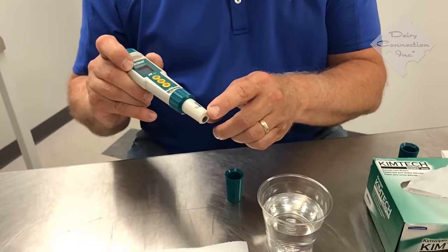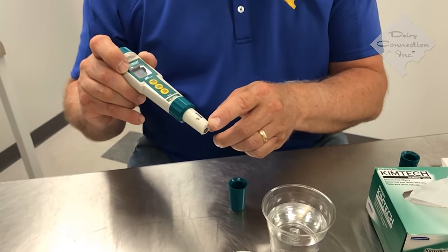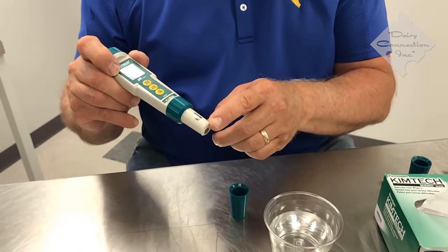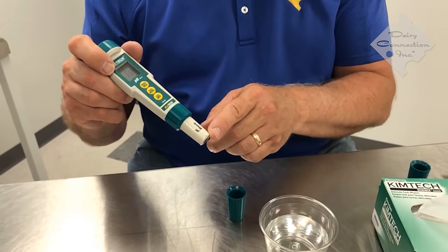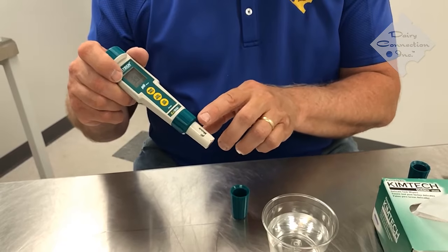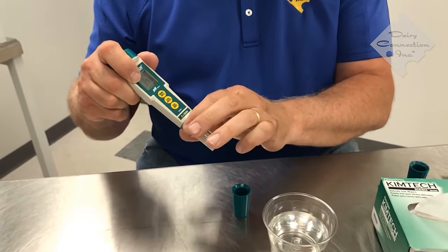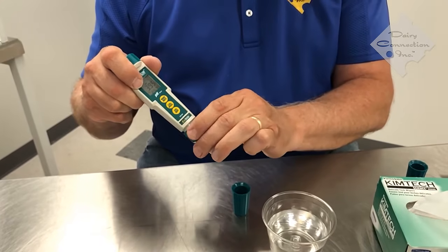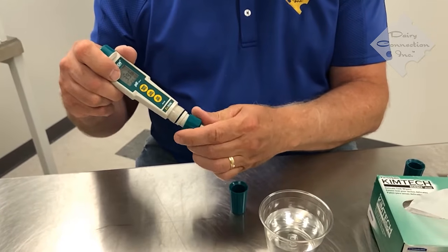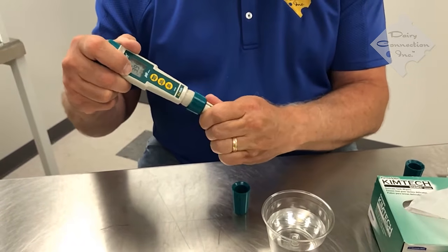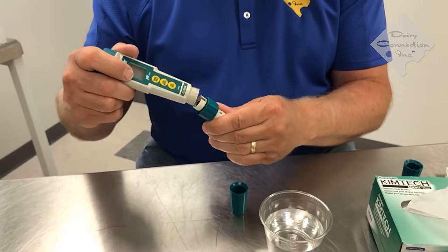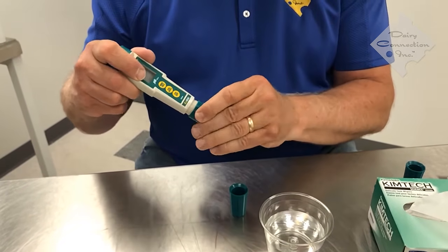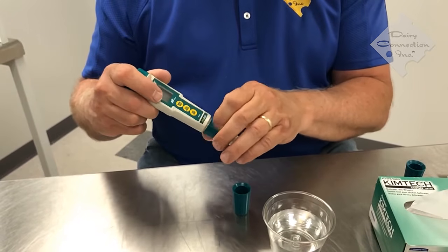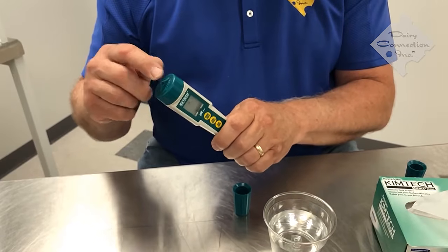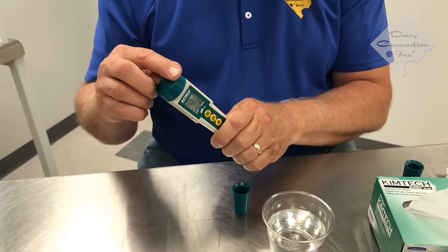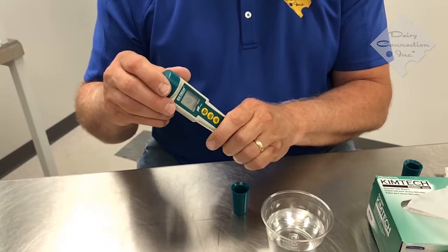And this is the critical point of maintenance of your pH electrode, of keeping it clear of calcium and protein and fat that are inherent with dairy products. If you're going to have a problem with the pH meter, this is the probe that's going to be replaceable, and it basically will just screw off, and you can replace this and still maintain the body of the pH electrode. It just simply is an electronic part that comes apart like this, and we replace that. The life expectancy of this electrode is usually about 1 to 2 years. The other area that you may have is the batteries. The batteries are under this cap. You simply unscrew the cap, and there are 4 batteries in there that can be replaced.